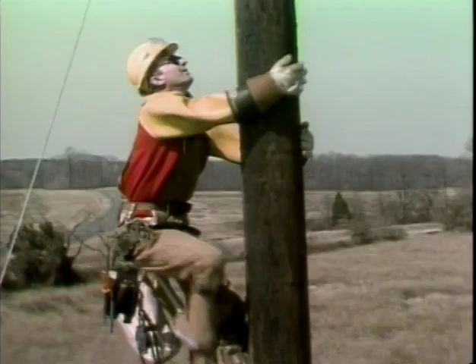Accidents, equipment malfunctions, and certain electrical conditions could cause the circuit to be energized when it comes time to perform your work. That's why you should always assume that a circuit is live until you've tested it. Let the testing prove whether or not a circuit is dead. Now, we'll look at three types of testers: noisy testers, stethoscopes, and phasing test sets, and see how they're used to test a circuit for dead. But first, let's discuss some considerations that apply to testers in general.